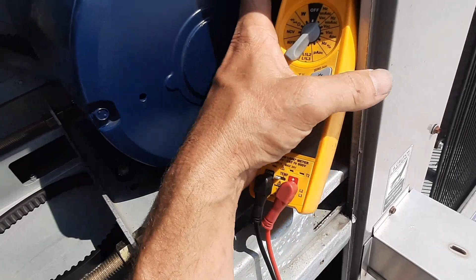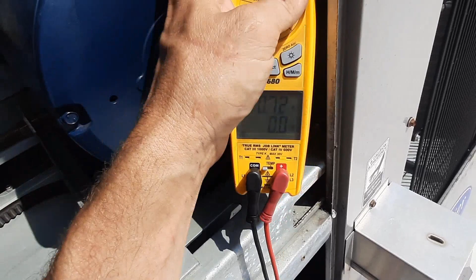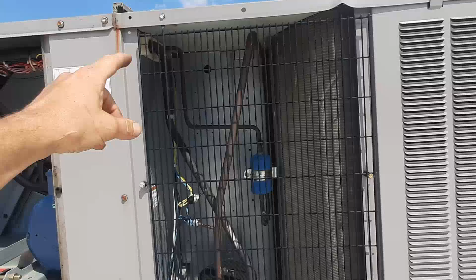So I went ahead and jumped it out. I got tired of waiting. I got fan motors. 0.7. I was pretty sure there wasn't gonna be a problem over here, so I went and plugged them all back in. Yeah, 0.7. 0.7. So as suspected, after I chased my wild goose all the way through my condenser section, fan motors are going to be okay. We got to figure out what's going on with the power exhaust, but that's where my problem lies. It took me a little while to get there, but you got to go through everything. In my experience, a lot of times, actually most of the time, it's in the condenser fan motor wiring, up along the rail, everything I checked first, obviously.